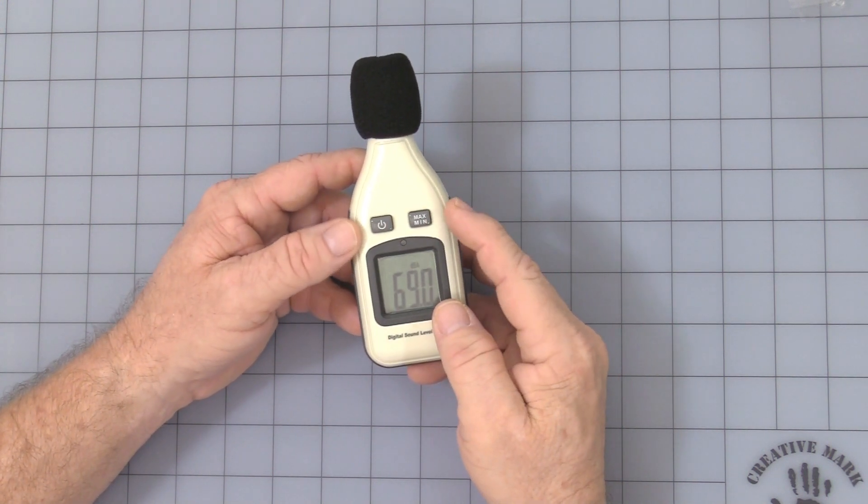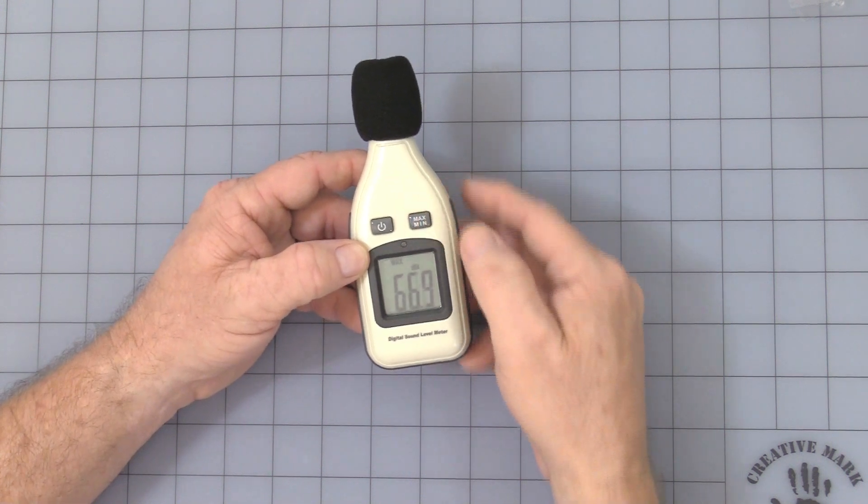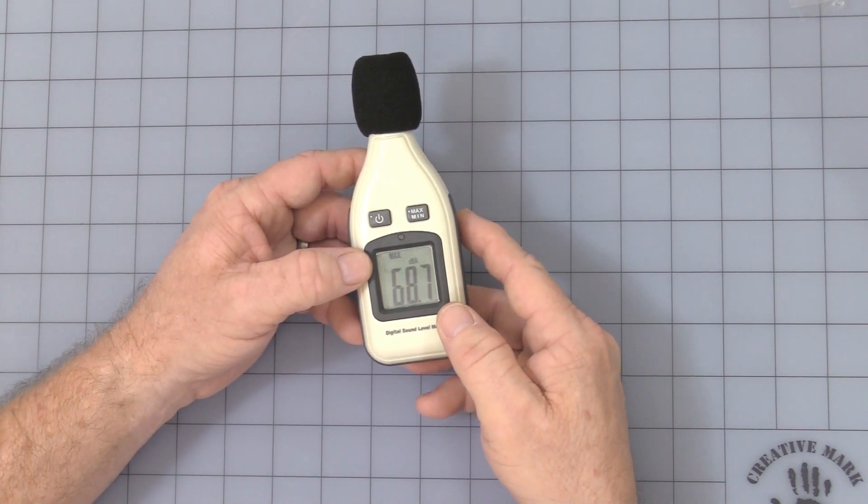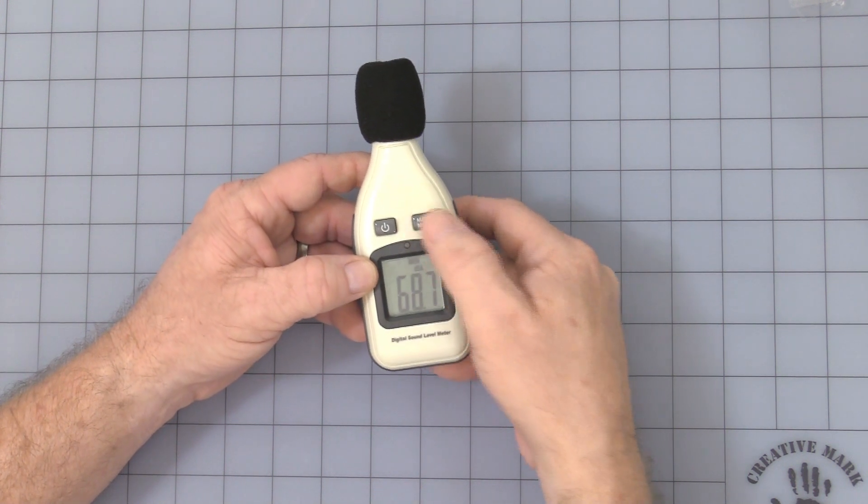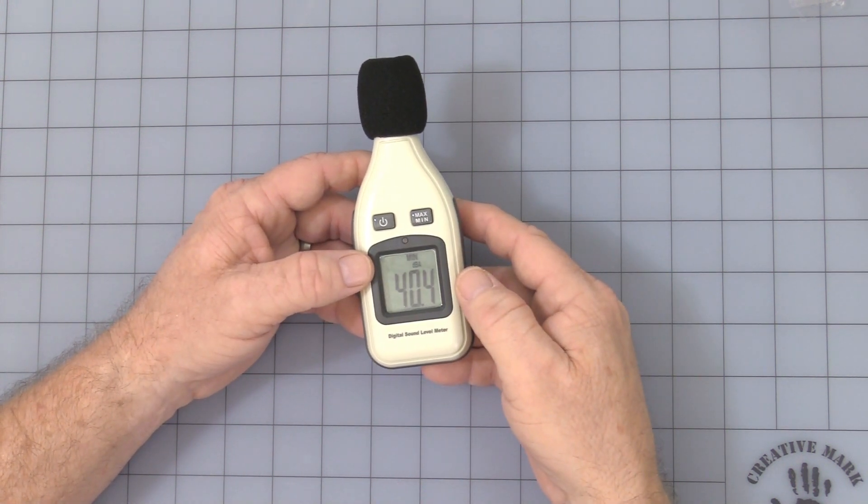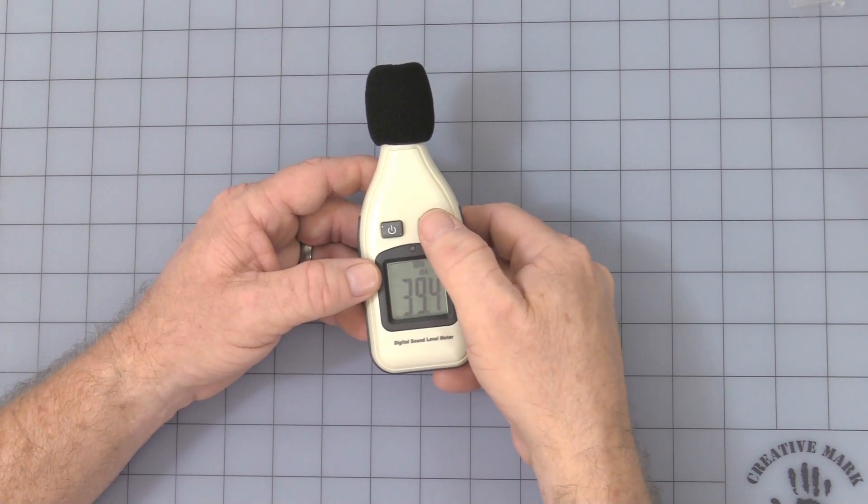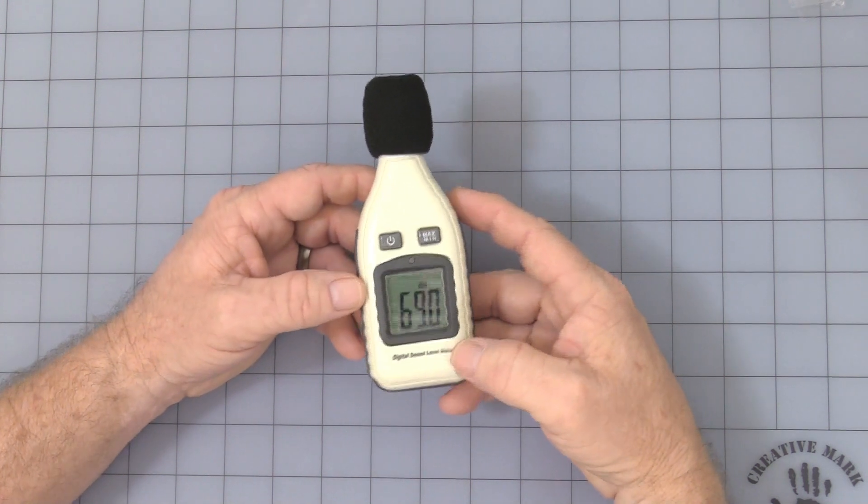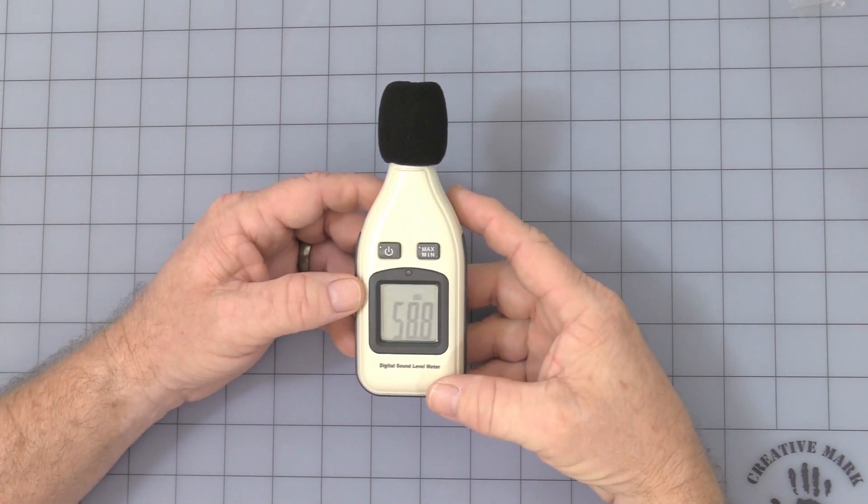Next button that you have is a minimum and maximum. I press it once, it displays the max reading. Press it again, shows you the minimum reading. Then press it a third time, it goes back to the actual measurement at the time.